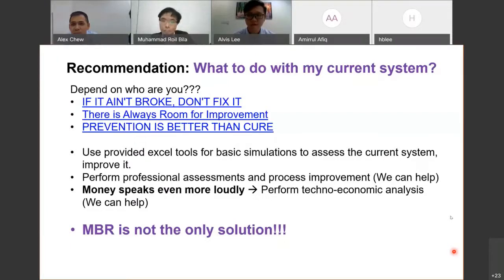Well, you can use the same membrane for up to 5-7 years. You just need to do intensive cleaning maybe once a year. So the replacement, the lifetime of the membrane, really depends on how you operate.